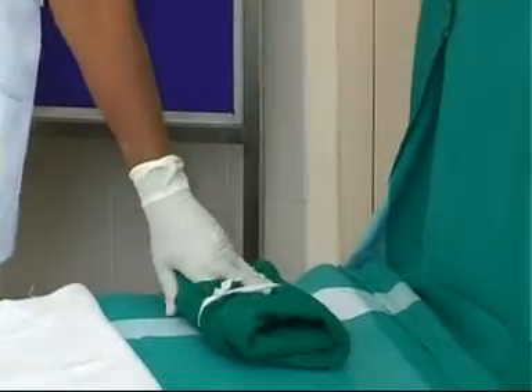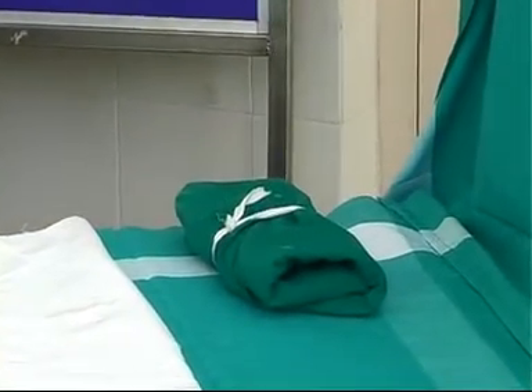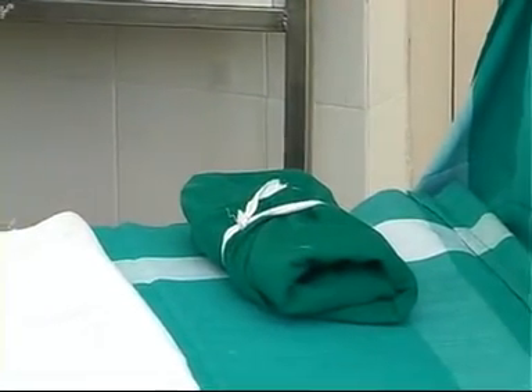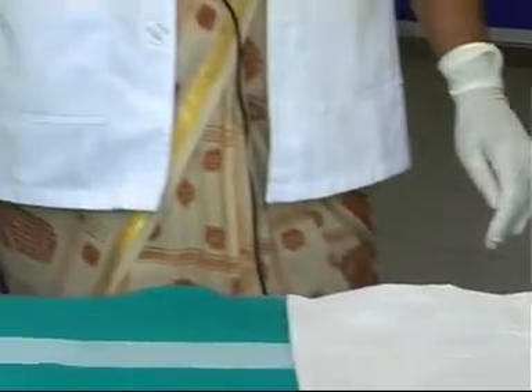This has to be kept in the autoclave machine at 120 degrees centigrade and 20 lb pressure for 30 minutes. After 30 minutes, turn the machine to fast exhaust mode for 15 minutes. After 15 minutes, again to vacuum dry for 15 minutes. When the autoclave machine has cooled, we can remove the pack from the autoclave machine and keep it in the sterile area. It is ready to issue to the ward.